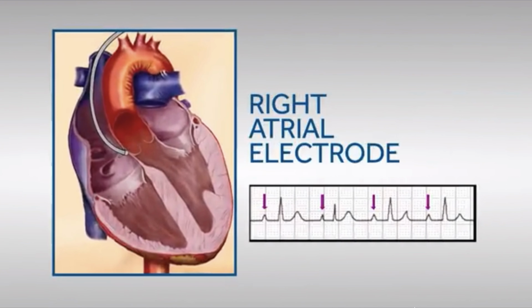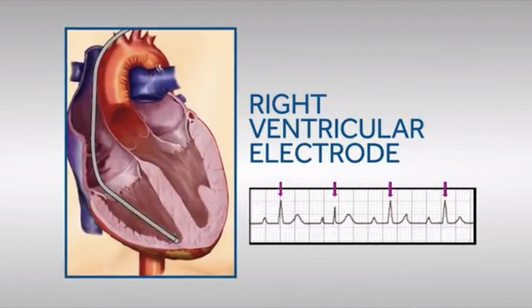Appropriate sensing results in every heartbeat being properly sensed. This means that when the lead or wire is located in the atrium, all P waves are sensed, and when the lead or wire is located in the ventricle, all R waves are sensed. It also means nothing extra is sensed, such as a T wave, which would be interpreted as a heartbeat. Threshold values are needed to determine the appropriate settings for output and sensitivity.